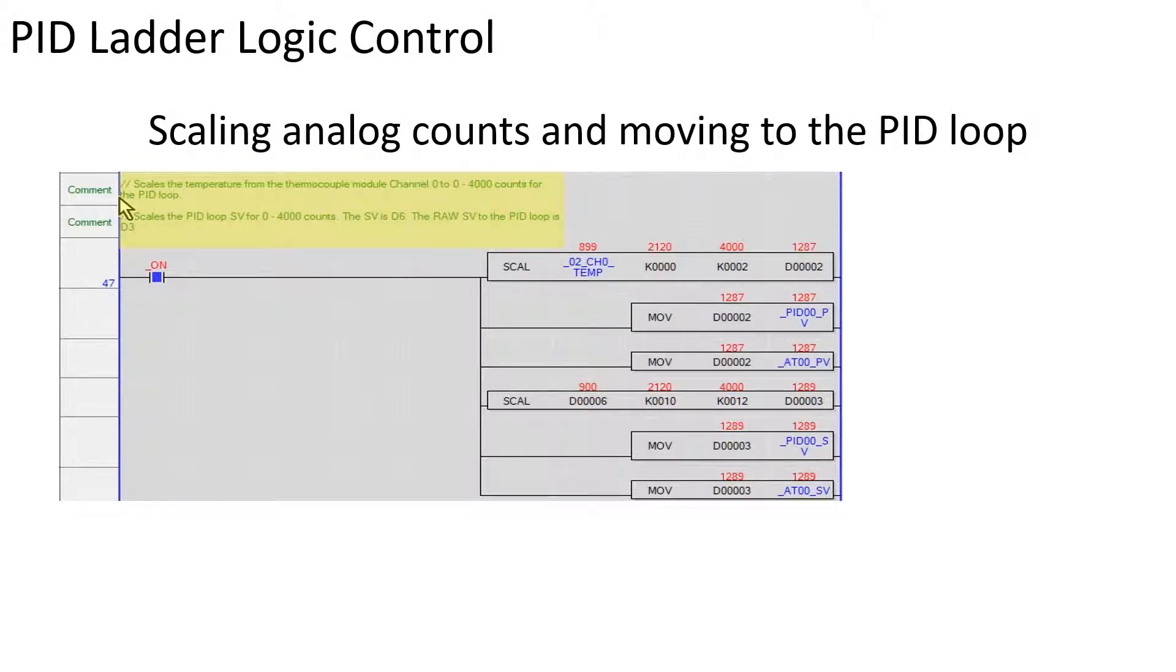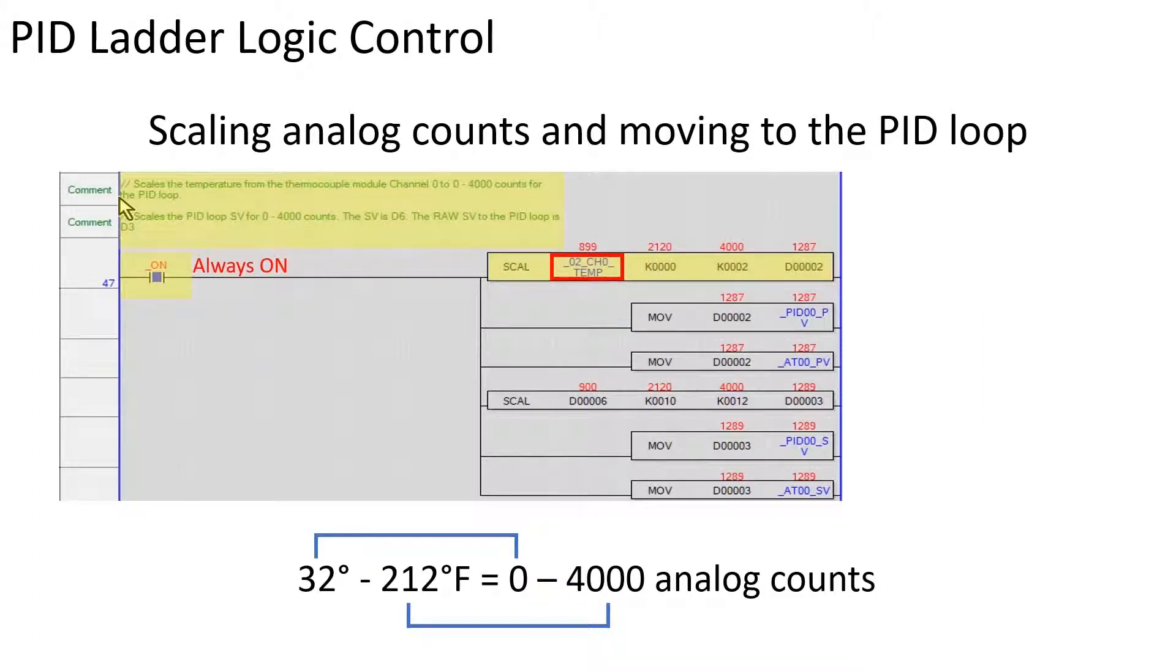In ladder rung 47, the PV and SV data in temperature units are scaled to analog counts. The PID loop uses analog counts correlating to the analog range of the MV output. The SCAL instruction shown is being monitored in an operating program. The thermocouple value of 89.9 degrees is scaled to a value of 1287 as shown. This scaled value is stored in memory location D2.